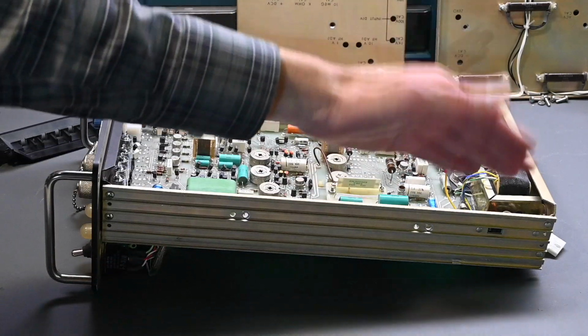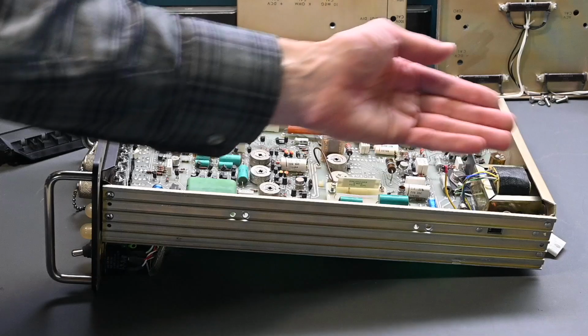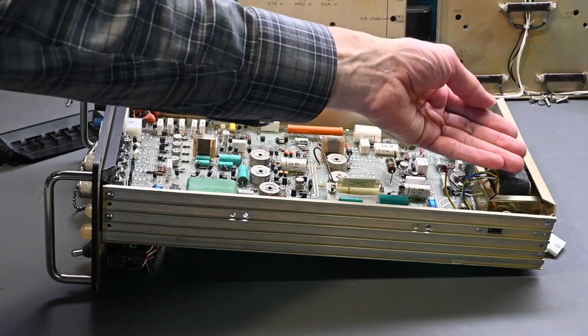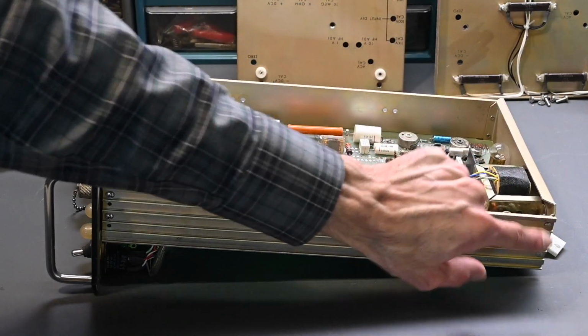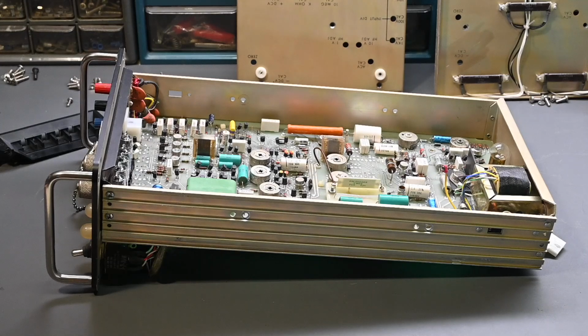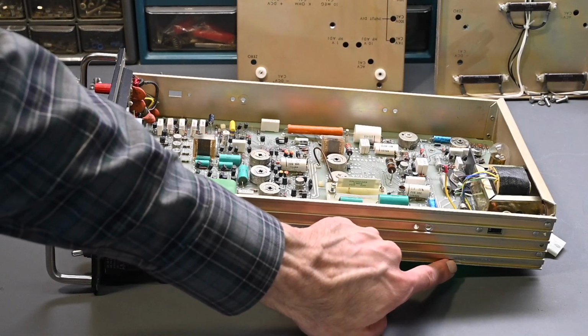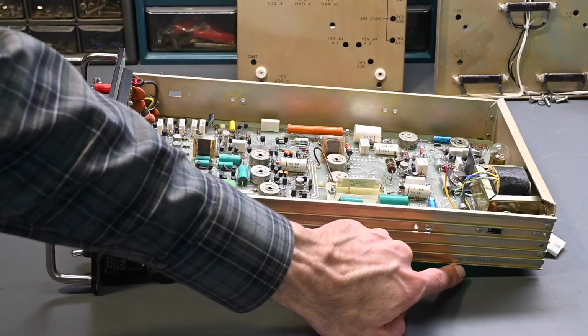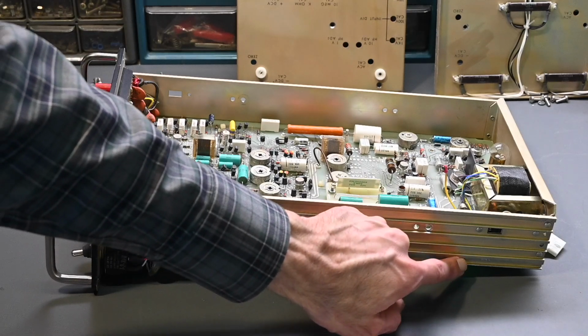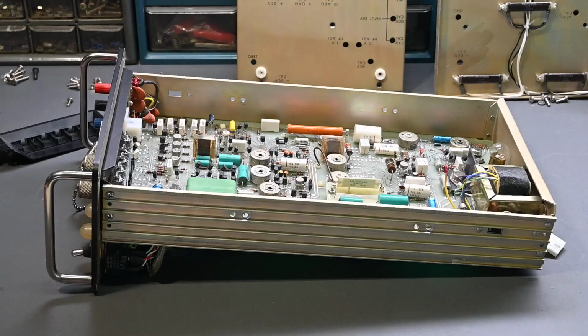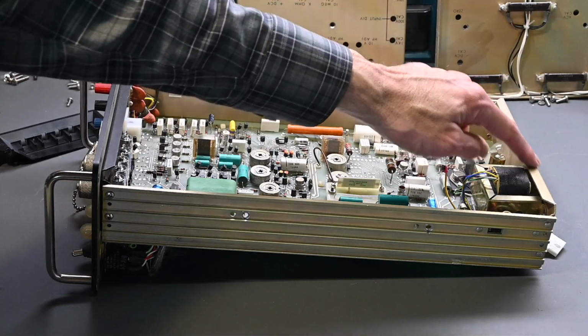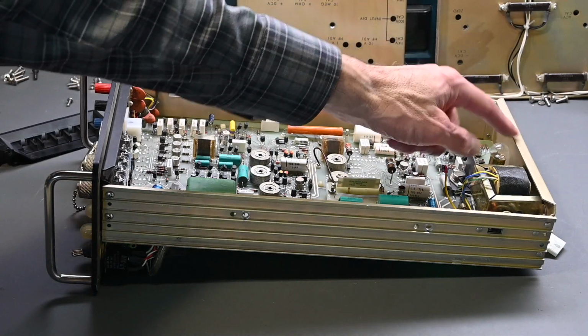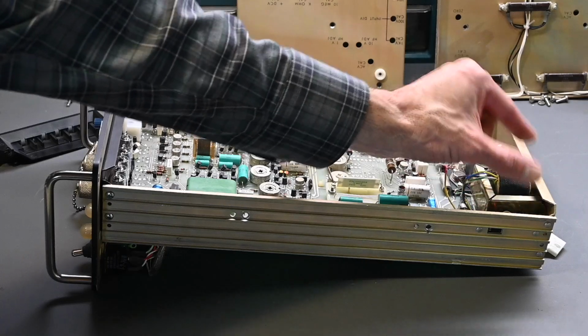So I was able to turn the instrument on its side, block it appropriately, and then press that down. There was just enough room to get in past that transformer and squeeze this back flat. Something like this, you never want to hit it with a hammer to try and straighten it out. There was also a dent, I don't know what happened on this corner right here, but it was kind of rolled up a little bit, and I straightened that back out and filed it smooth, so that turned out very nice. This was bowed in considerably in the back right here, so I straightened that out. The transformer was loose on its mounting screws, so that's been tightened up.